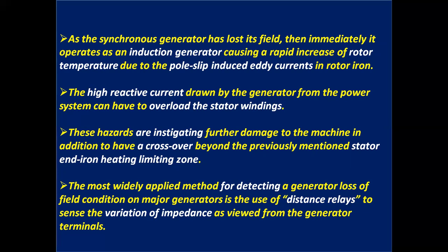These hazards instigate further damage to the machine, in addition to crossing beyond the previously mentioned stator end iron heating limiting zone. The most widely applied method for detecting a generator loss of field condition on major generators is the use of distance relays to sense the variation of impedance as viewed from the generator terminals.